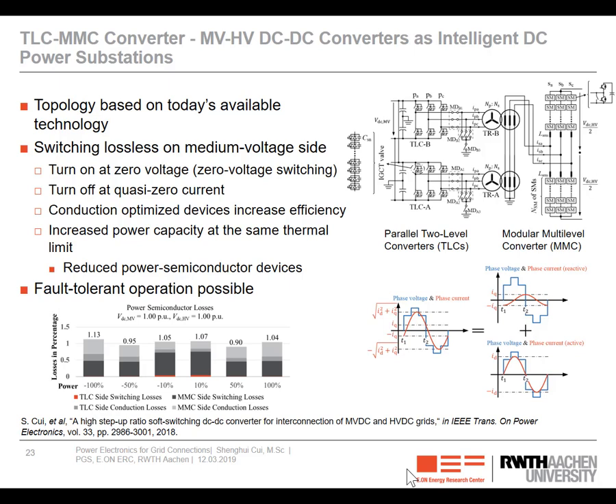And we should keep in mind that the motivation of developing DC grid is to integrate renewable energies, right? And for renewable energies, the efficiency at partial load conditions is way more important than at full load, because most of the time renewable energy generation is working in partial load conditions. And here, if you look at this converter, in full load situations the semiconductor loss is around 1.04%, and at 10% of the rated power, at such a low power, you can still achieve very low semiconductor losses.